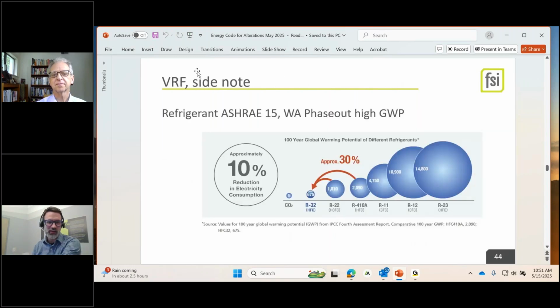We're doing a refrigerant changeout that makes all refrigerants A2Ls, which are very lightly flammable. Ask at the end what my fire protection engineering side thinks about this changeout. But with that, we also get a bunch of requirements for fire-rated chases. VRF is a lot more complicated because you can release enough of a charge into one room. There's a lot to address there. It is no longer automatically a leading contender for what we're going to do in an existing building changeout.